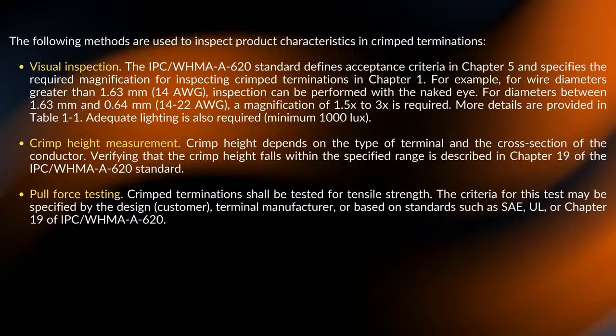There was nothing in there. It really comes back to them having requirements for the crimp terminations, but there's also the equipment you're terminating to that you have to look at. That's where you get into deciding if you're violating code by using a crimping method or not. For people who want extra insight on where to look, this is where you go.